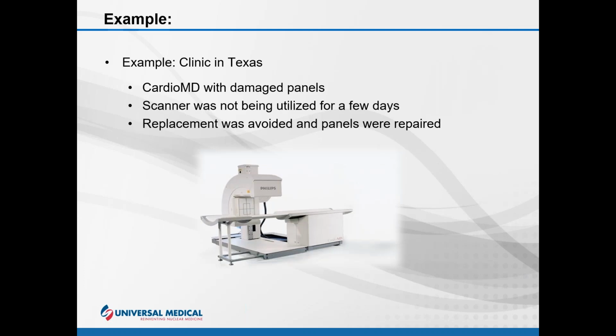We had a great example here of a repair option. We assisted a tech at a clinic in Texas with a CardioMD system that had damaged panels. We evaluated the problem via phone. It was determined that the tech would need to purchase replacements. Speaking with the tech a little further, he knew they had a few days between scheduled patient scans. We gave them the option of sending the panels to us for repair. We were able to evaluate the parts, and we were able to repair and repaint the panels. We returned the parts to the tech the next day, and the tech was able to remount the panels and resume scheduled scanning. And the tech was very pleased with the timely manner the parts returned, and the cost savings of not having to purchase replacement panels or having an unnecessary service call.